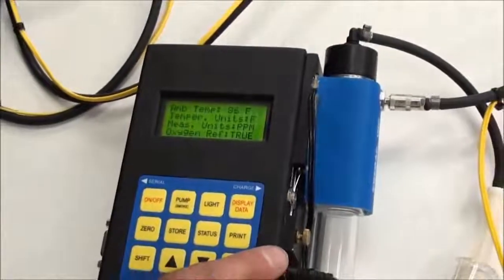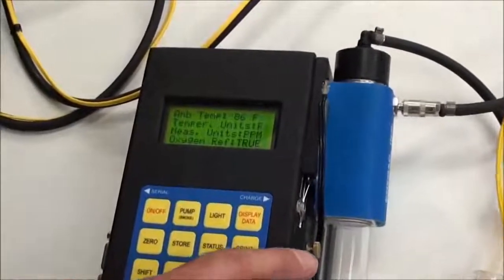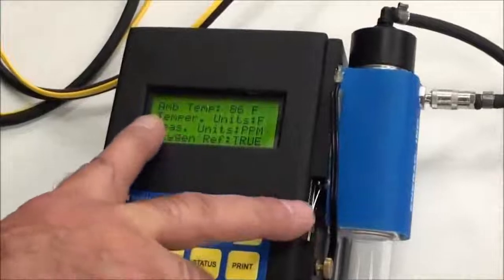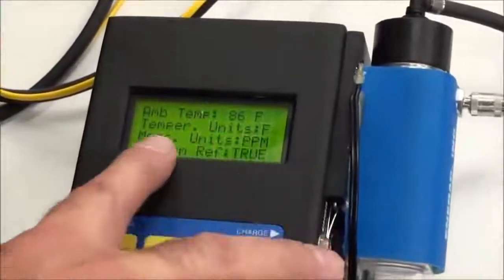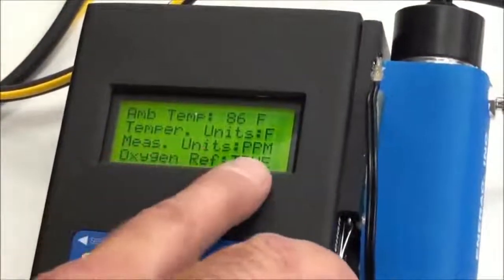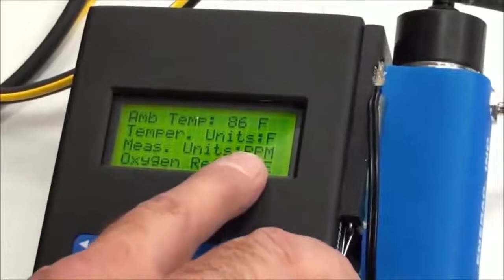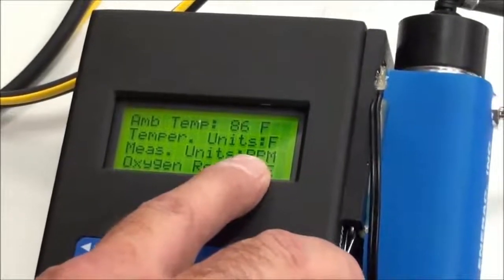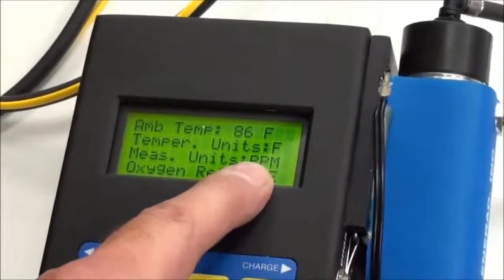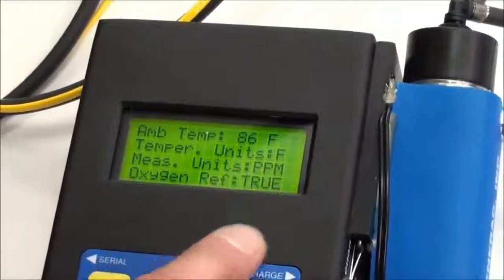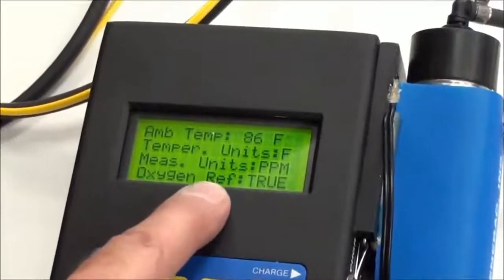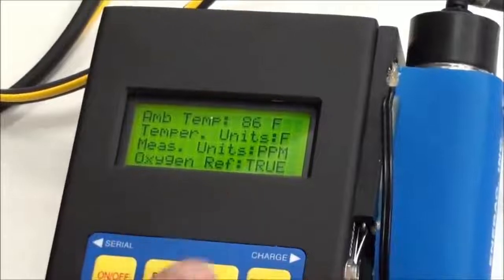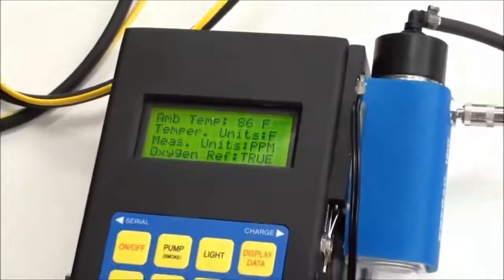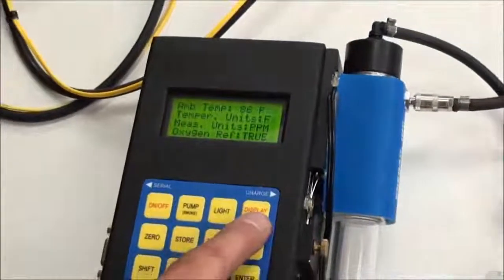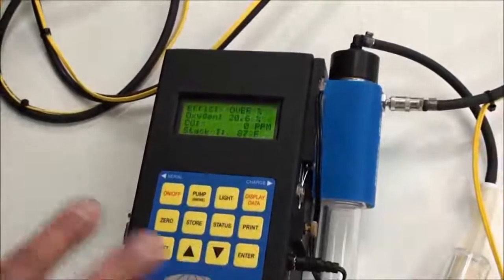The next screen is the ambient temperature, the temperature units in Fahrenheit or centigrade. Measurement units, you have several options on that. You can do ppm, grams per brake horsepower hour, pounds per million BTUs. Then there's the oxygen reference. If you need that, you can go in and you can set that. I'll show you that in the menus. At this point, you're pretty much ready to go.